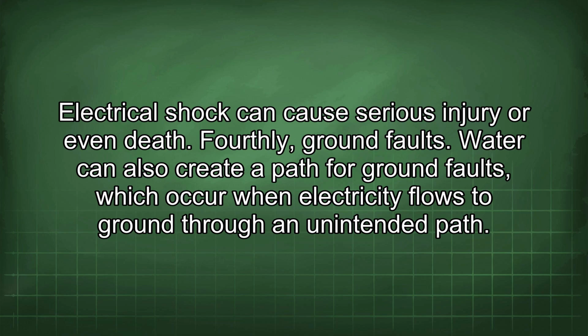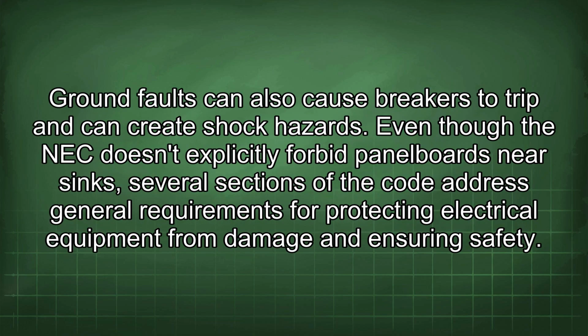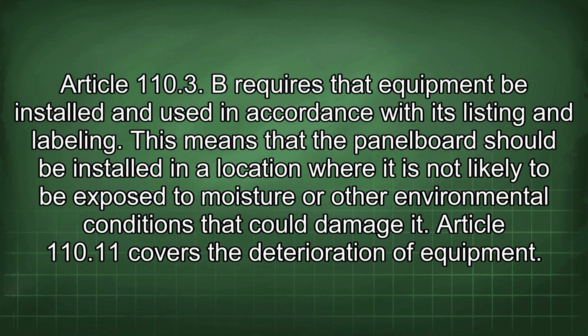Fourthly, ground faults. Water can also create a path for ground faults, which occur when electricity flows to ground through an unintended path. Ground faults can also cause breakers to trip and can create shock hazards. Even though the NEC doesn't explicitly forbid panel boards near sinks, several sections of the code address general requirements for protecting electrical equipment from damage and ensuring safety. Article 110.3(B) requires that equipment be installed and used in accordance with its listing and labeling. This means that the panel board should be installed in a location where it is not likely to be exposed to moisture or other environmental conditions that could damage it.